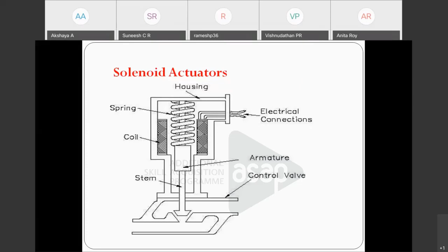There are different criteria to choose a particular actuator for a particular application. We have different applications, so what are the selection criteria? One thing is usage factors, meaning compatibility, temperature range, and hazardous area. These are important factors. You cannot place all the actuators in all the places, because the performance will be affected by environmental conditions like temperature and the hazardous area.